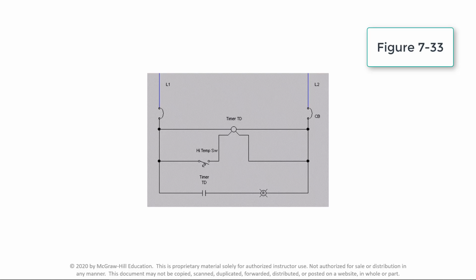The time setting of this symmetrical timer is 1 second. The timer is triggered into operation upon closure of the high temperature switch. The timer's output contact closes and opens at 1-second intervals to operate the pilot light. The pilot light continues to flash on and off as long as the high temperature state exists.